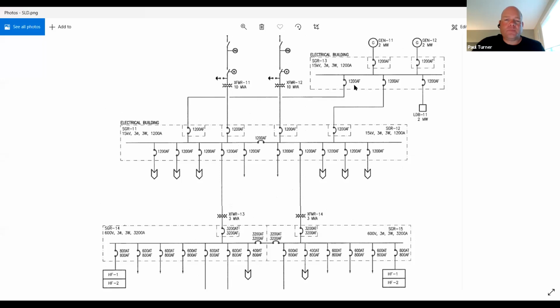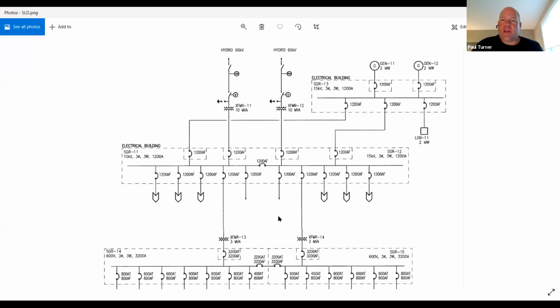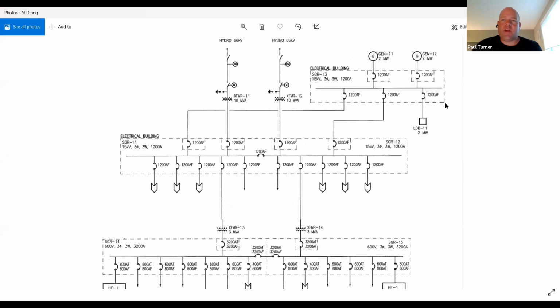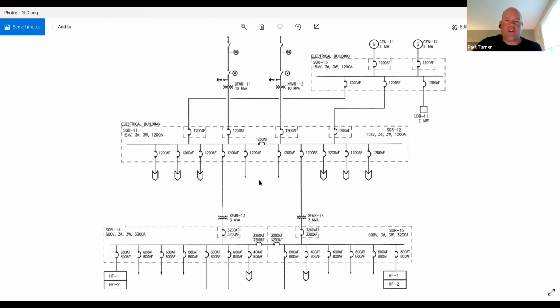So if we think about the basic systemization of this system, it could be broken down into a few different aspects here. I would consider the gensets as one mechanical completion, one turnover of the system, separate from the rest of the system. That package with the static load could be defined as one mechanical completion for that scope of work, defining the physical equipment that's required, listed by tag number, as well as the documentation required for that turnover, that mechanical completion. I would then consider the basic electrical distribution to energize up to the 15 kV system and 600 volt system as another mechanical completion.